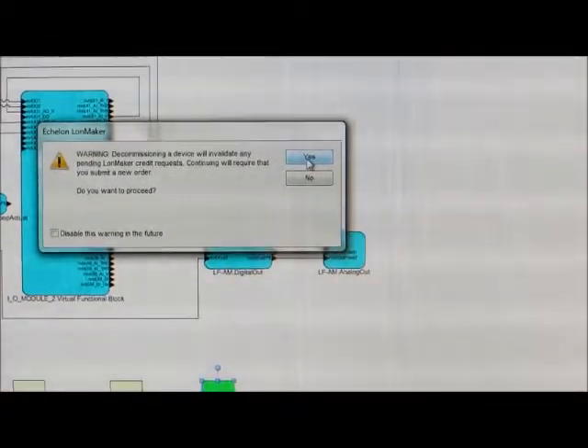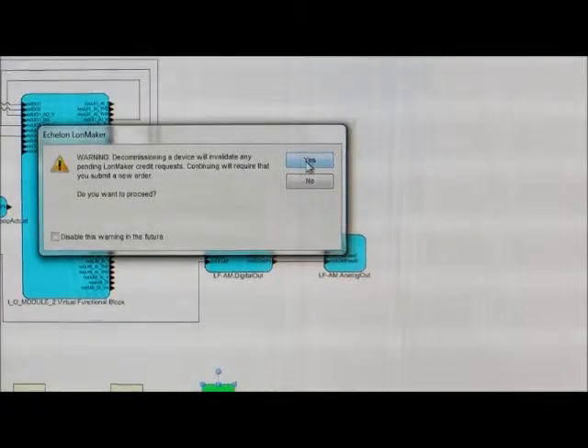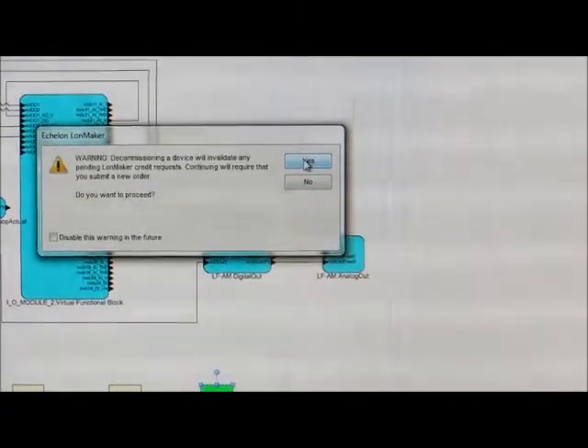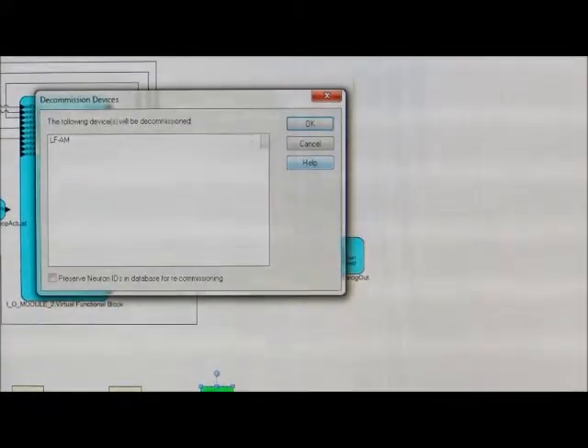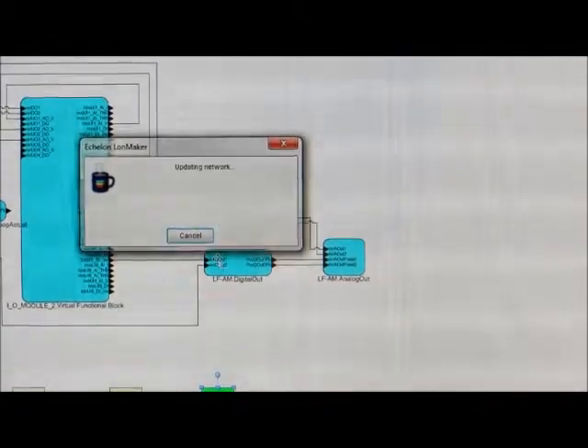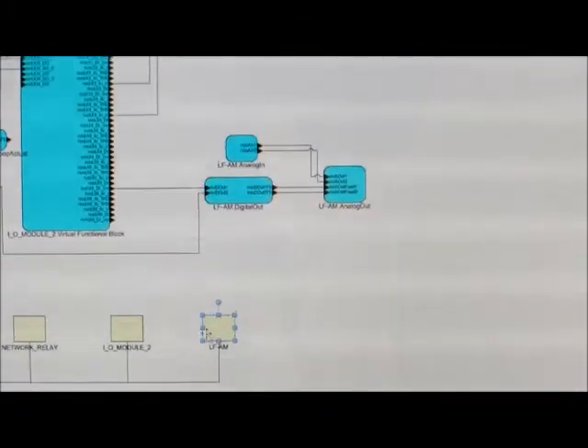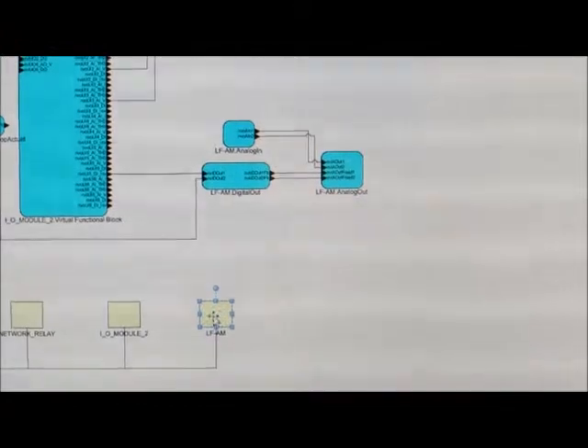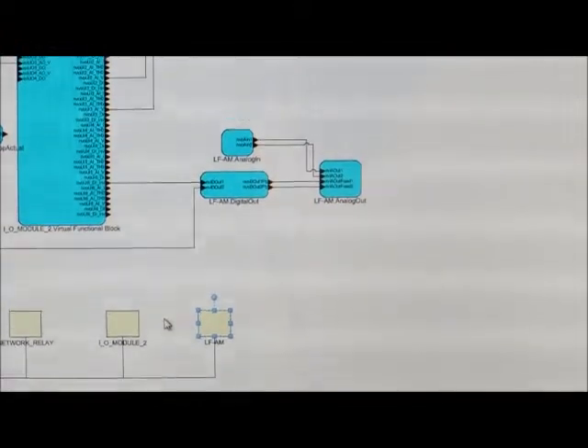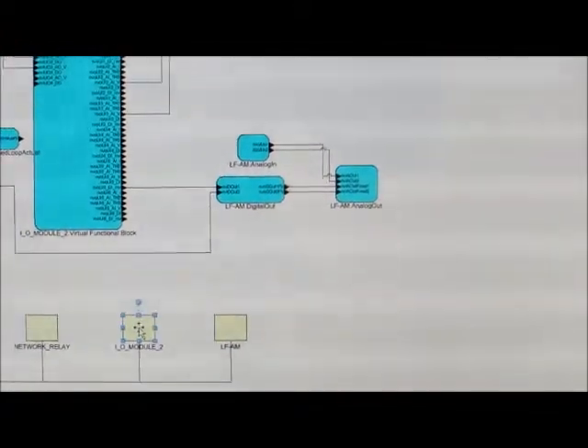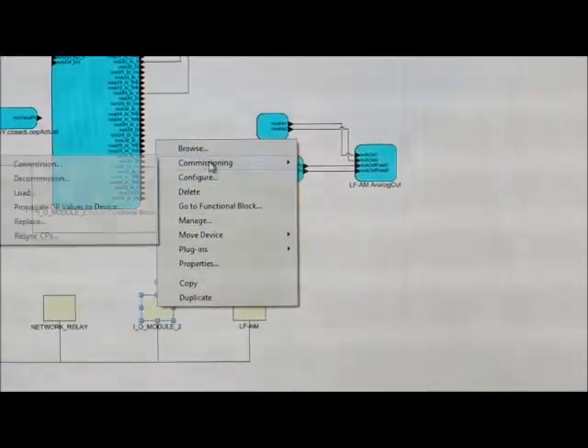So if you start with 25 and you decommission a device, you'll get 26 back you can use. So hit yes, click OK, and it'll decommission the device. So you can see the box turn from green to a tan color. Now if we want to commission a device, we'll right click on it, go to commissioning, commission.